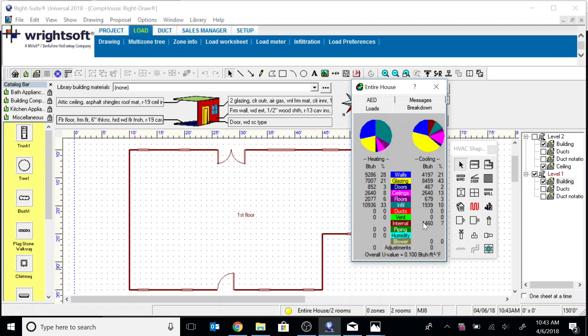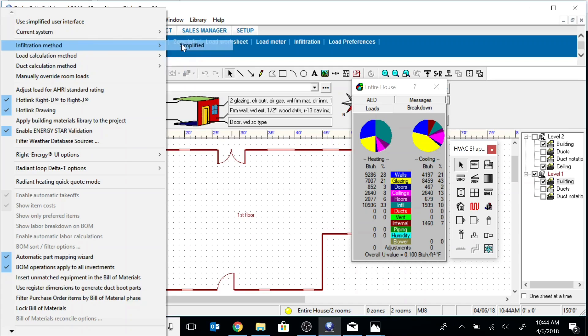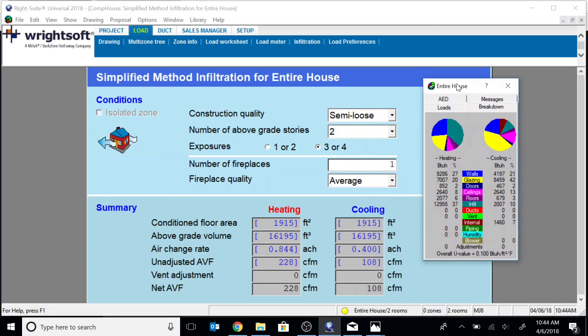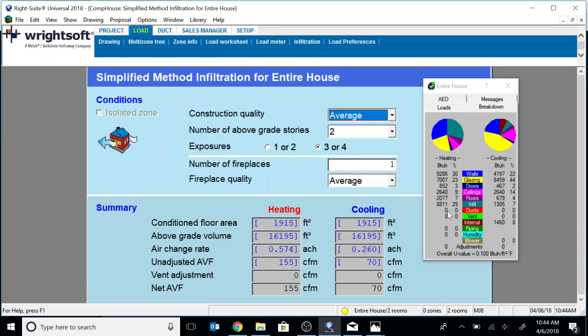I used the blower door to do the infiltration, and we can see that with my blower door number — which is pretty favorable, about 7.75 ACH50, roughly a one to one ratio of square foot to CFM — we're at 33% in heating and 10% in cooling. Those are the BTUs right there. If we were to change the infiltration method to simplified, which is standard, and select semi-loose — which I see all the time on loads — average construction quality, you can see that average is considerably better than where I had it.